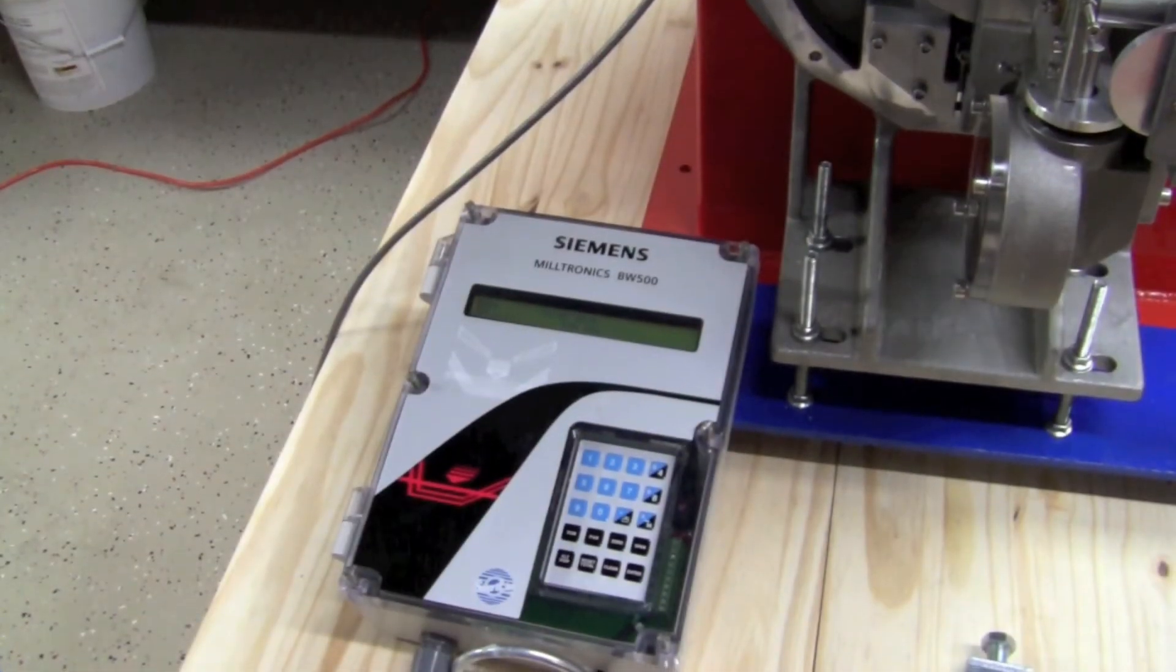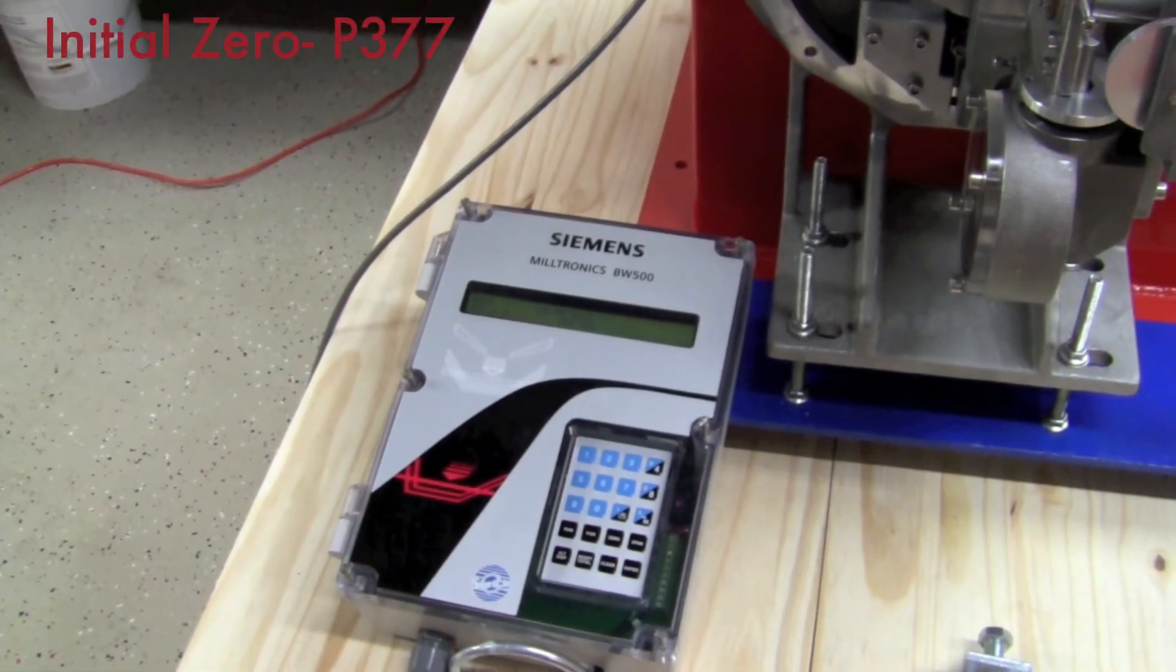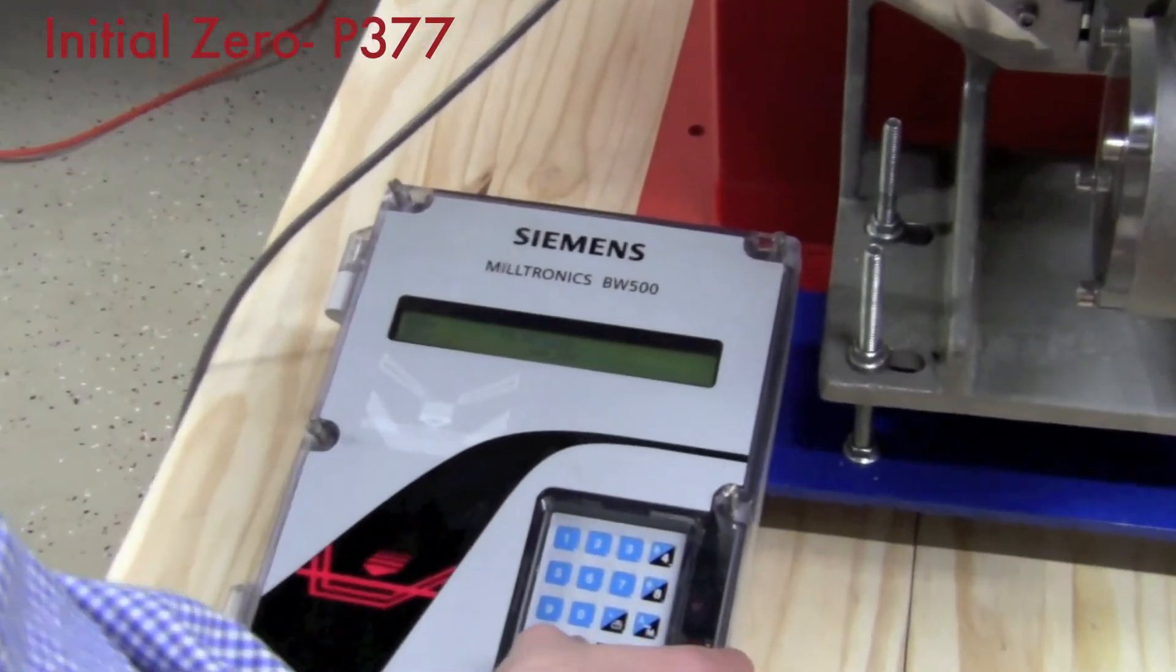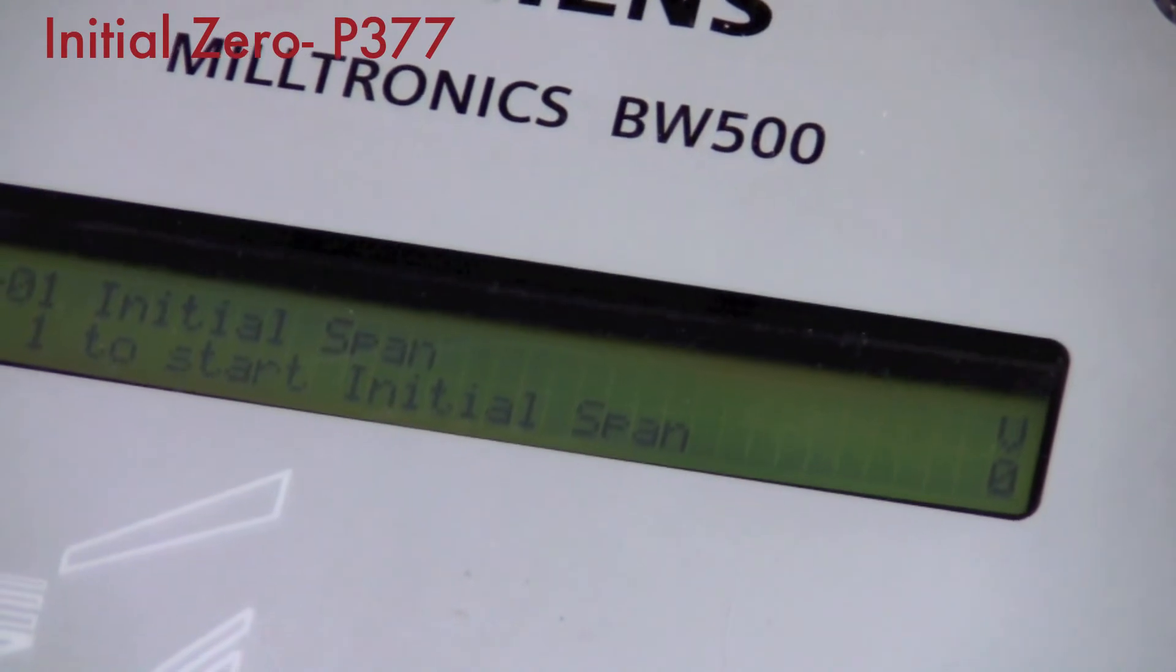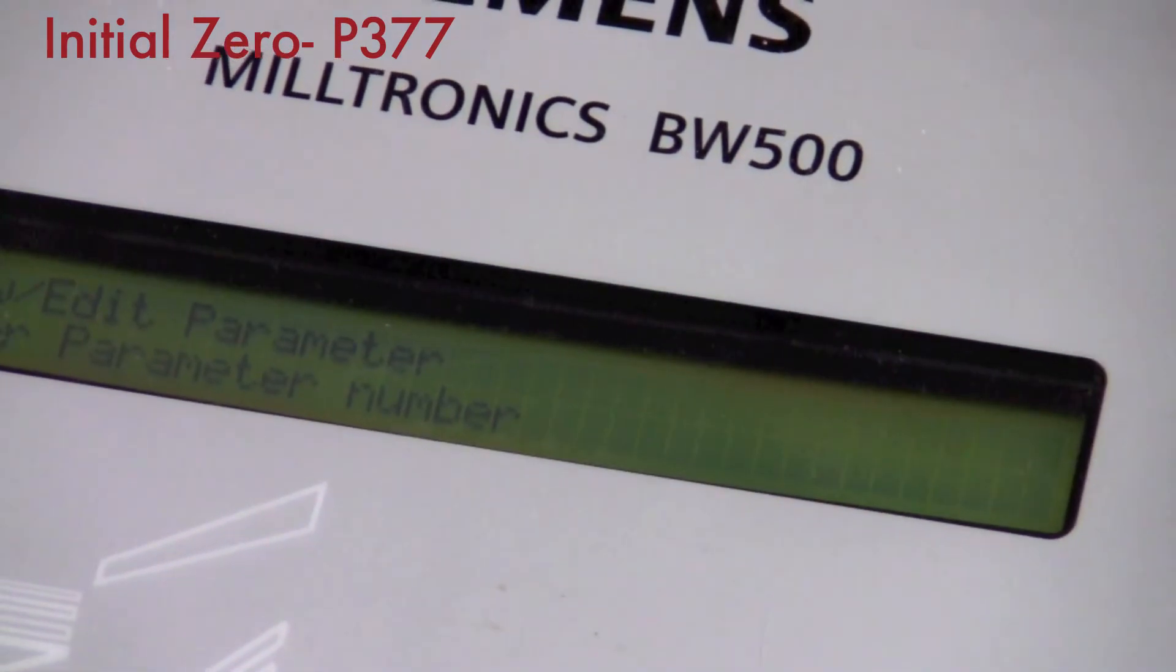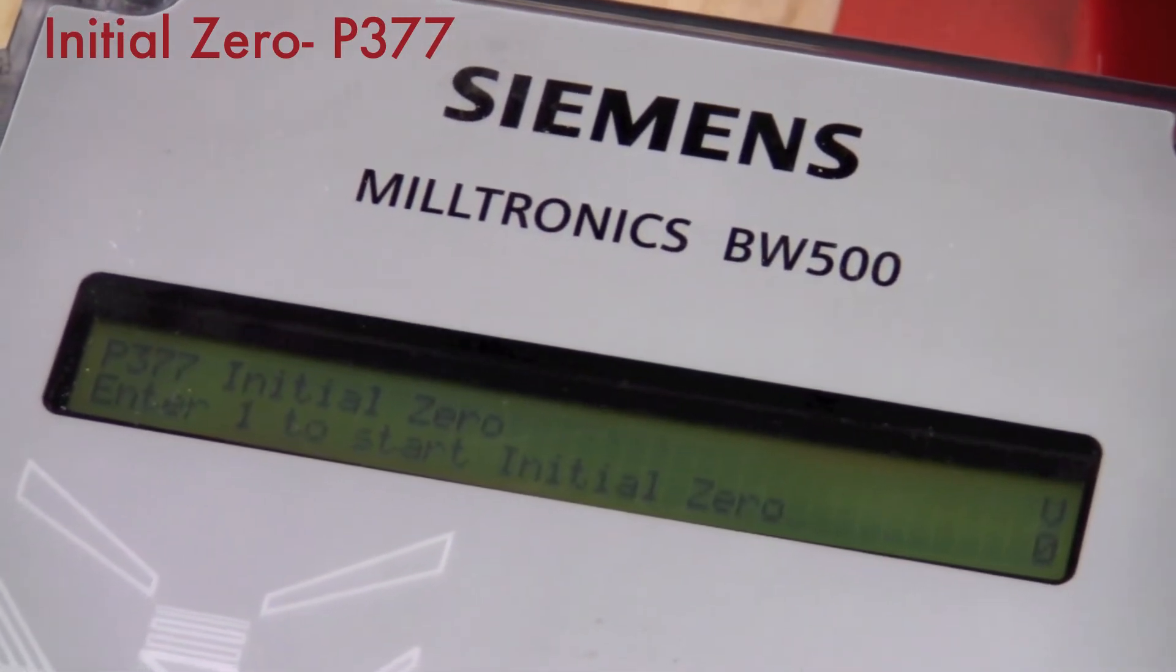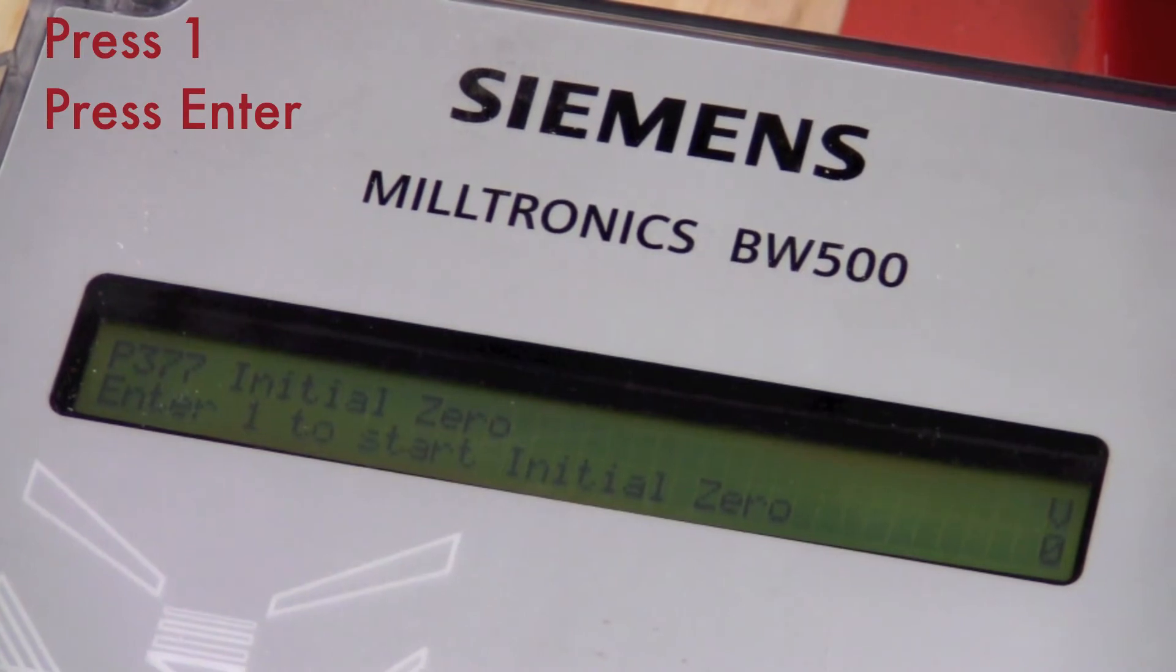Once you've calculated your test rate, you will then need to do an initial zero and an initial span. Initial zero is parameter 377. You need to make sure that the test weight is off of the sensing head and press one to start.